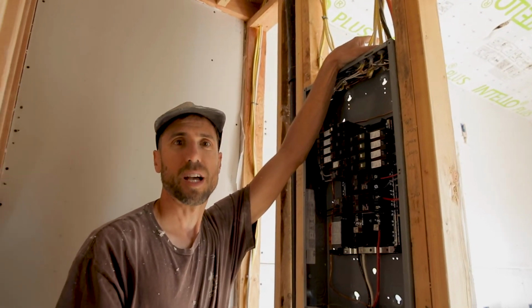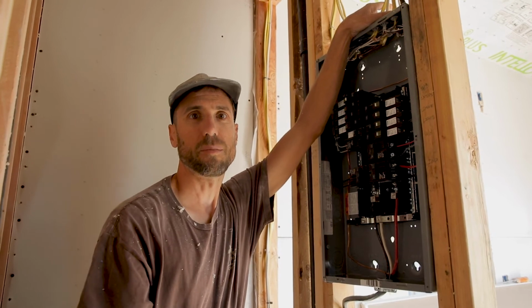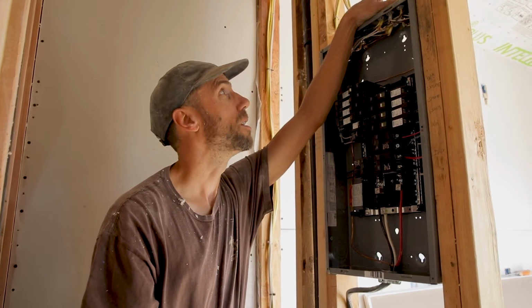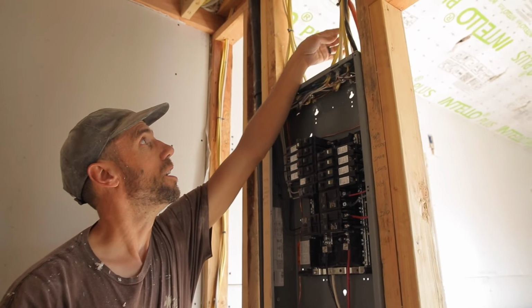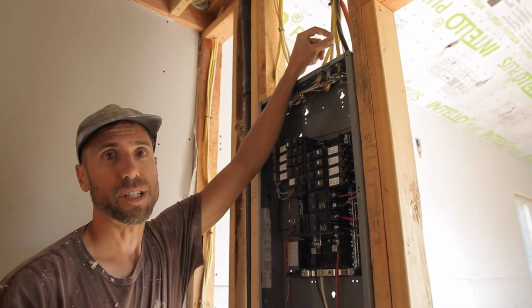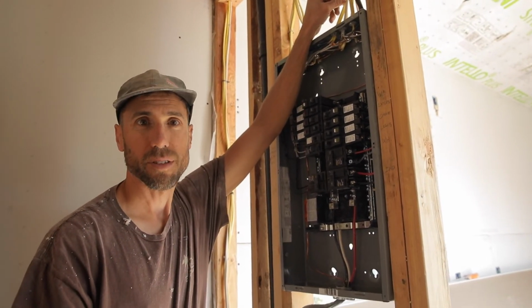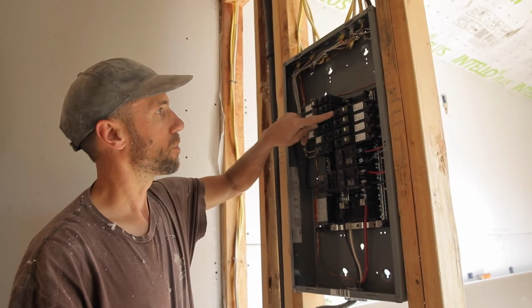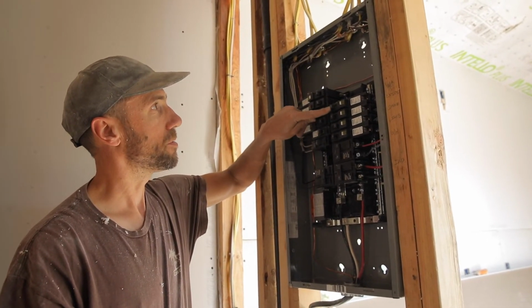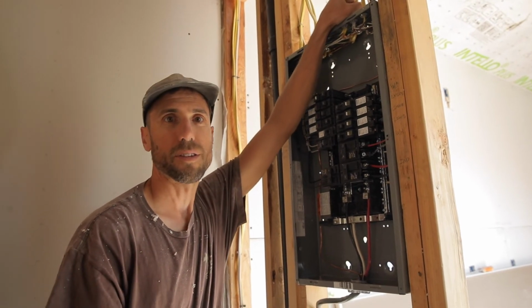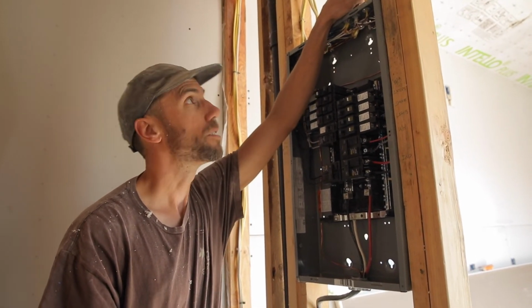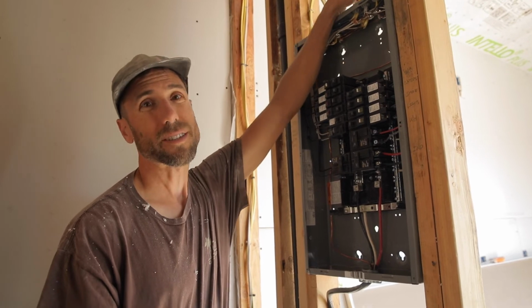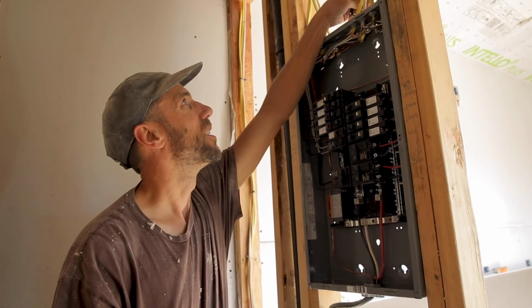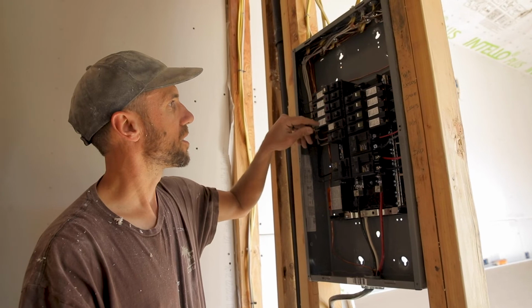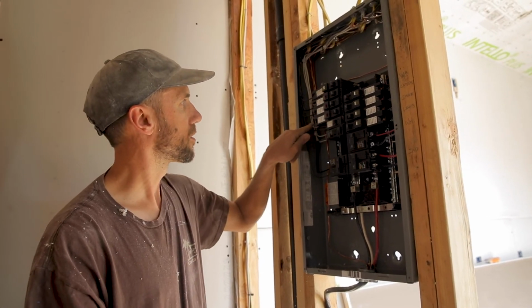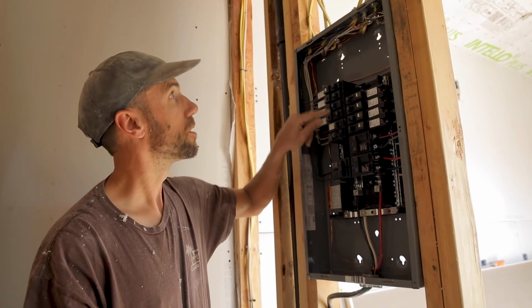We measure wire size in what's called wire gauge. It's a unit of measurement for wire diameter. So our smallest gauge here is this white wire right here. This is 14 gauge wire. This is good for 15 amps. So all of those 15 amp breakers, you can see they're labeled here. Any 15 amp circuit is going to have this white wire here, 14 gauge. And our next is 12 gauge wire, and that's good for 20 amps. So you notice any of our 20s here, we've got one. This is going to one of those yellow cables.